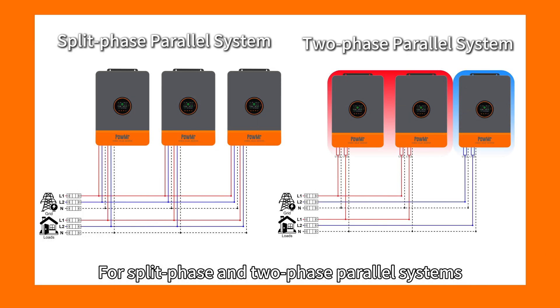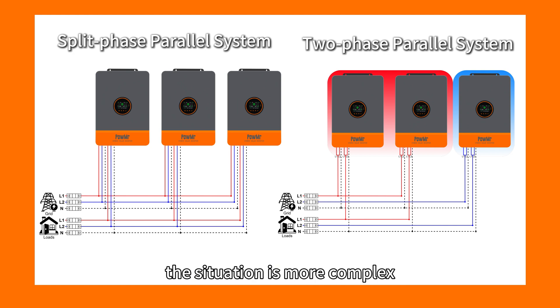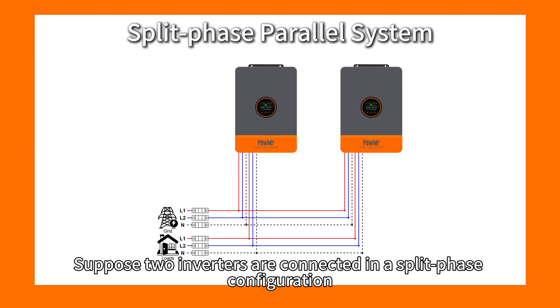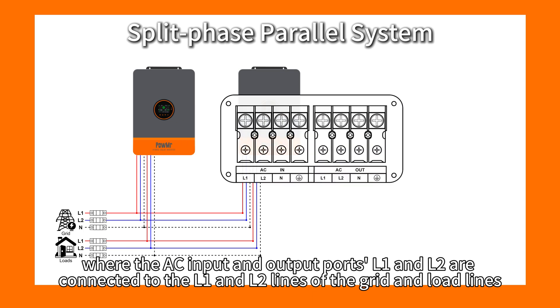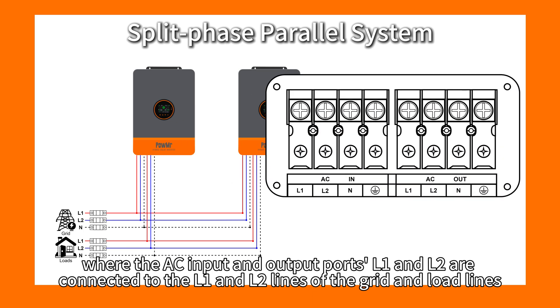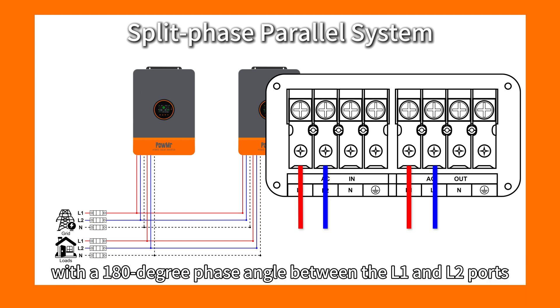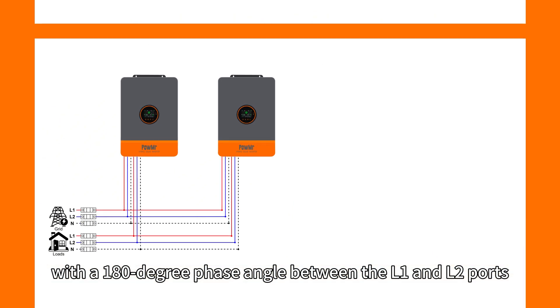For split-phase and two-phase parallel systems, the situation is more complex, which is the focus of today's discussion. Suppose two inverters are connected in a split-phase configuration, where the AC input and output ports L1 and L2 are connected to the L1 and L2 lines of the grid and load panel, with a 180-degree phase angle between L1 and L2 ports.